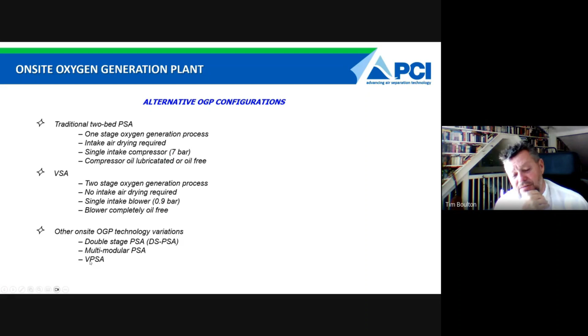Okay, oil lubrication versus oil-free. We're talking now about PSAs. The big advantage of oil lubrication is its price. Typically, the oil lubricated compressor will cost around 70% less than the equivalent oil free, depending on the country and your supplier situation. What that then gives you is a much lower capital expenditure of your complete PSA system. So oil lubricated systems very often, especially in low and middle income countries, where budgets are very often much more limited, can seem to be a very attractive alternative. There are, however, disadvantages to an oil lubricated system.